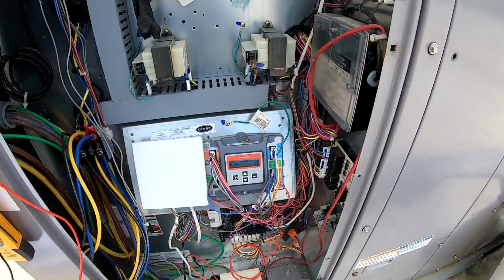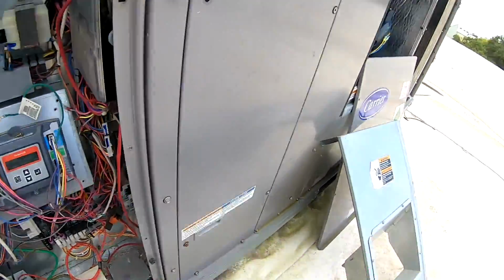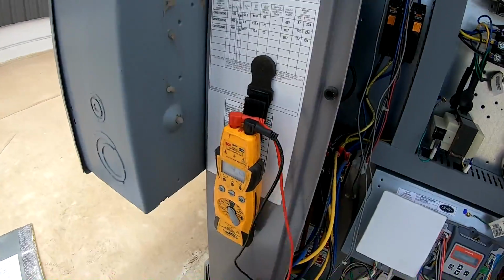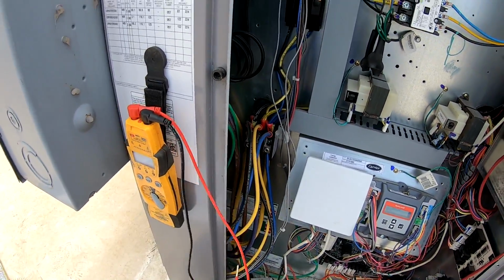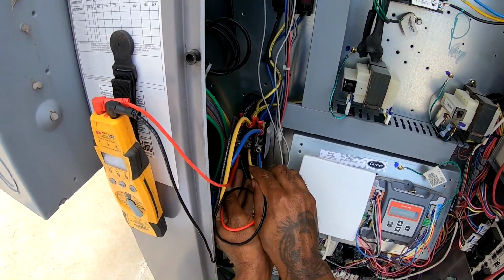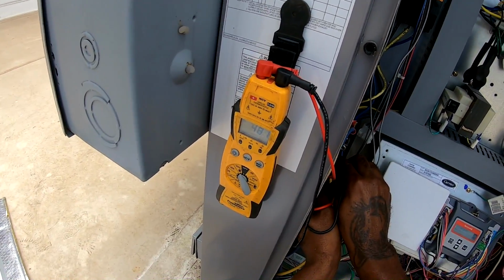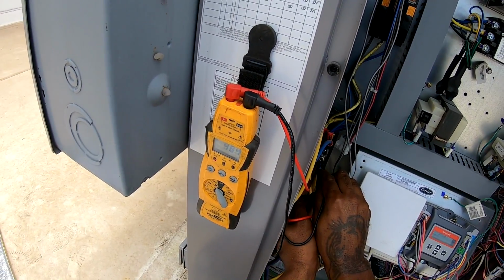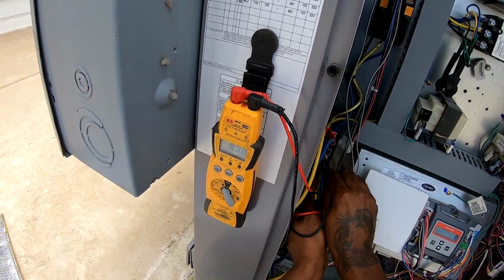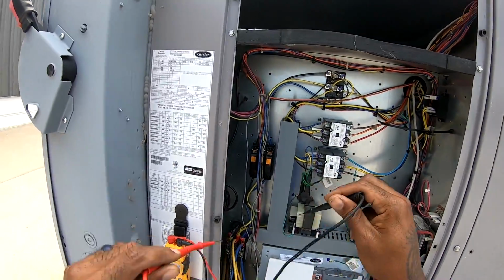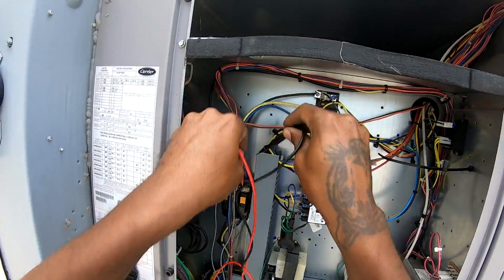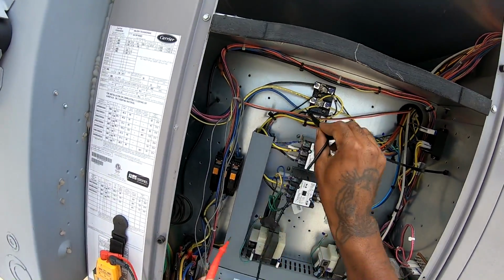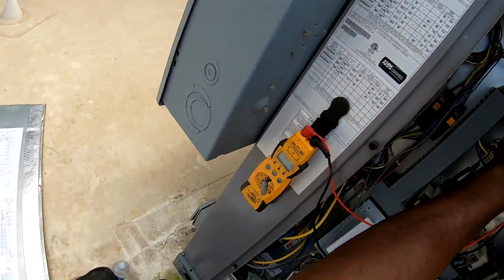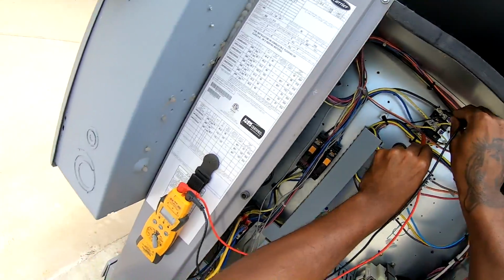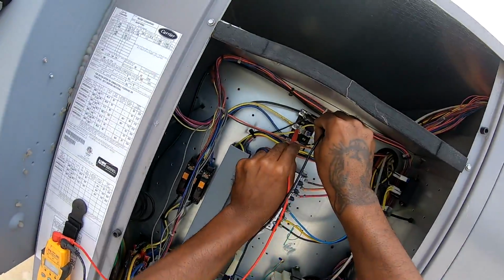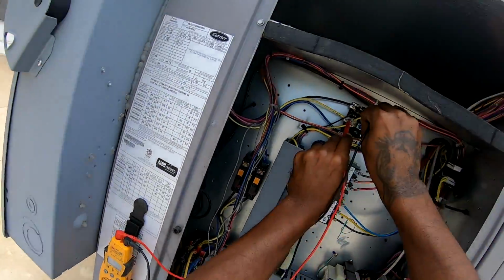So I'm just gonna let the unit reset, but I'm gonna check my incoming voltages coming to the unit, make sure we're good phase to phase. So I got 480, 480, and 2 to 3 I got 480. Check this incoming load side, see what's going in. Got 480, 480, and 480.